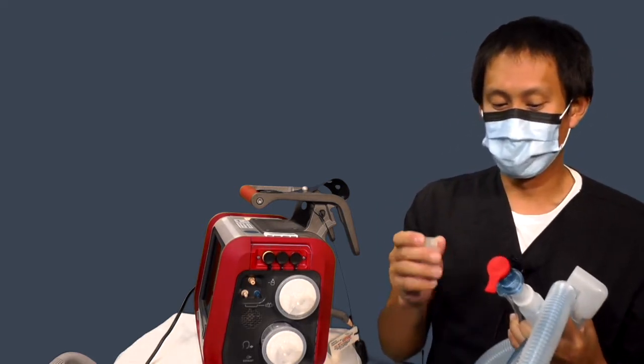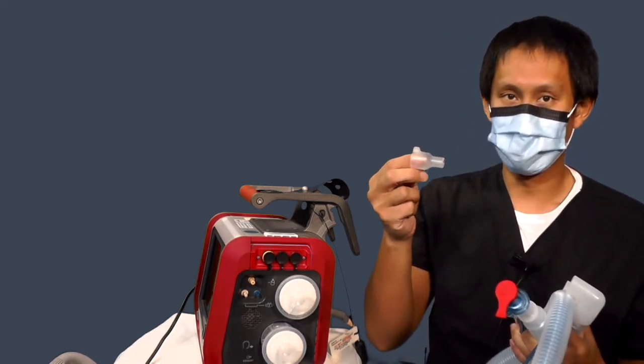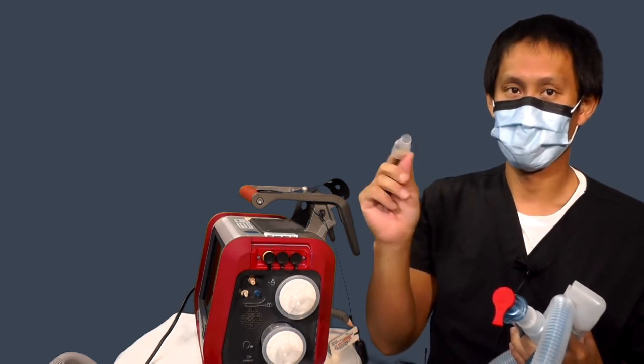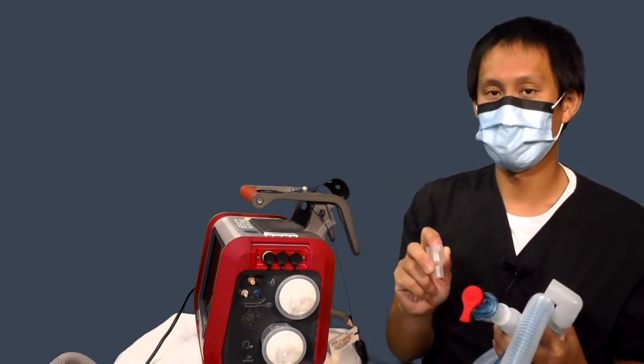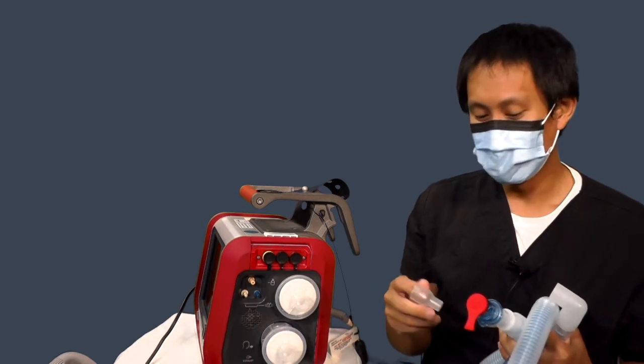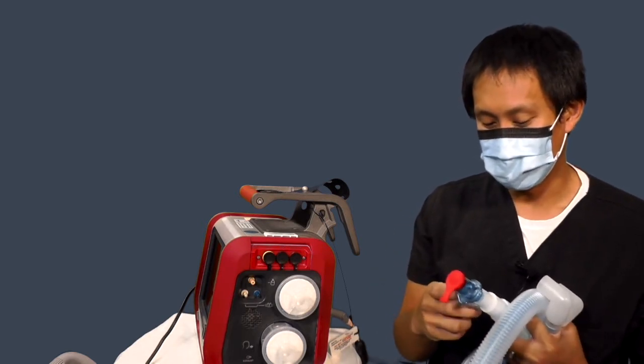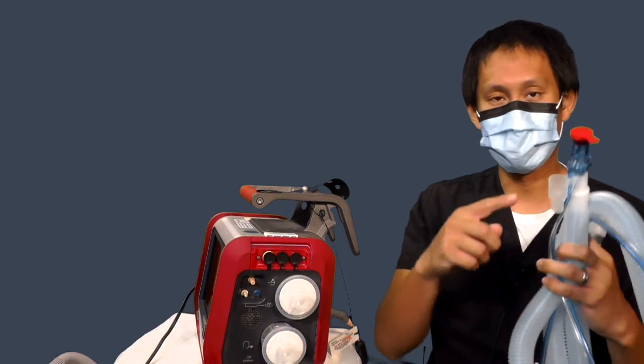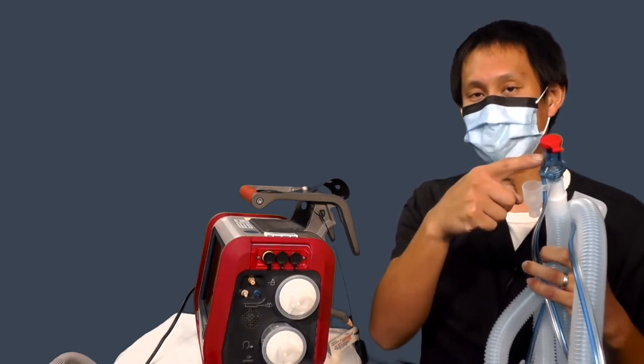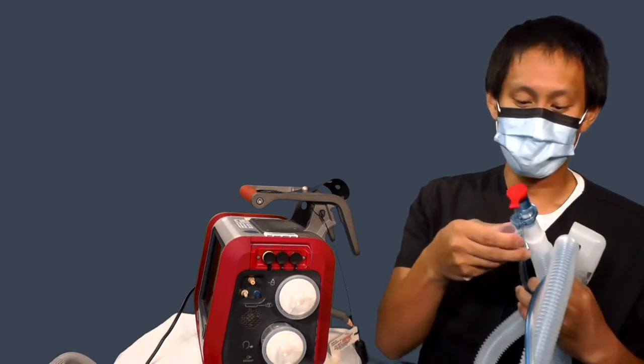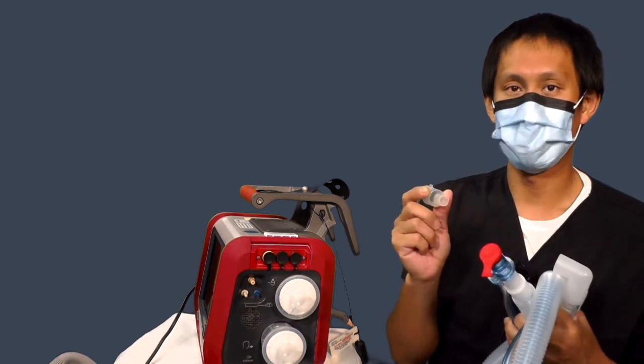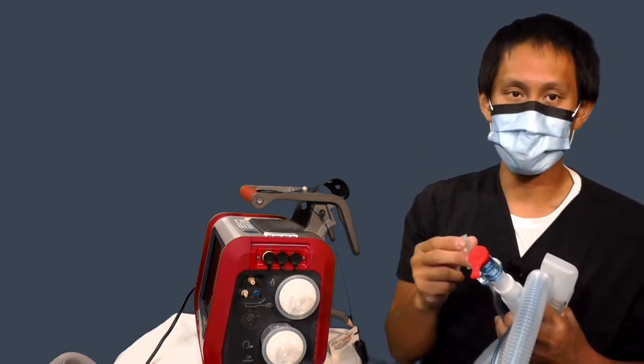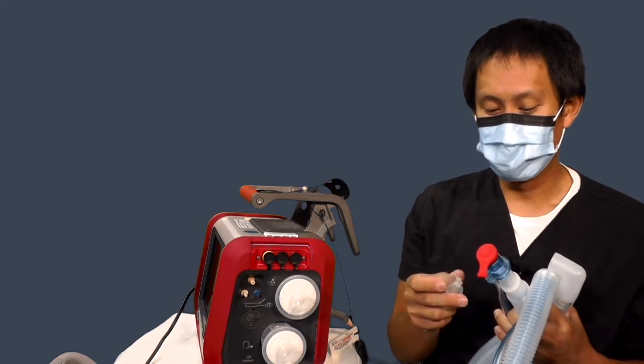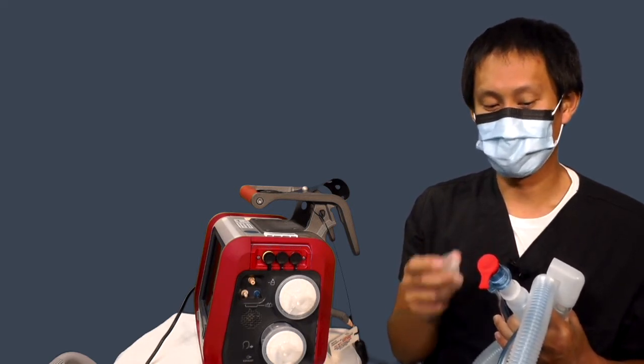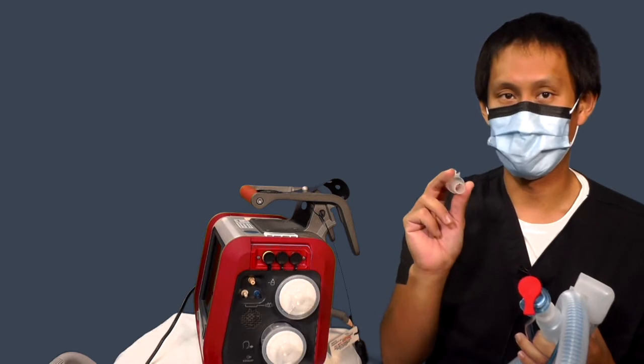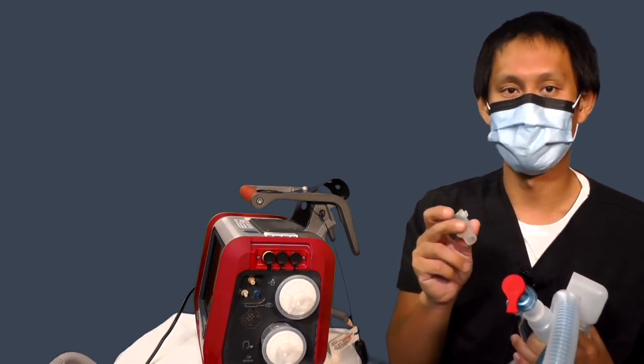What you'll notice in the kit too is there is an adapter. This adapter sometimes comes off when you open up the package. Make sure you try to keep it intact. It's usually clipped at the top right next to the flow sensor. This piece is only used during calibration. If you lose this piece, you do not need to open up another piece, and I'll show you how to do it without the adapter once we get to calibrating the system.